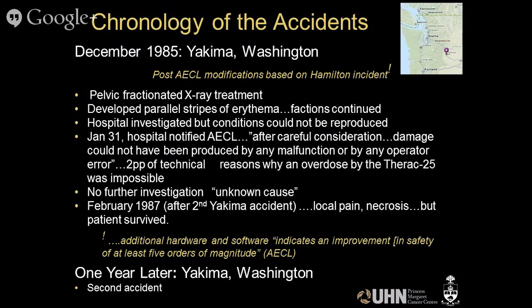There were investigations such as whether this could have been caused by abnormal sensitivity that was exacerbated by the fact that the patient had an electric blanket. But when you measured the width of the wires in the electric blanket, they were different from the widths of the stripes, and that wasn't an explanation. So lots of explanations were looked for to try and explain this away. But it was considered, after AECL analyzed this, that it could not have been produced by malfunction or operator error. And there were 2 pages of technical reasons given why this machine could not possibly overdose. There was no further investigation. It was put down to unknown cause. The patient had significant symptoms, but survived.